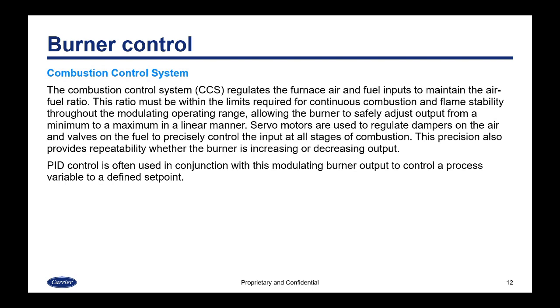The combustion control system regulates the furnace air and fuel inputs to maintain the air-fuel ratio. This ratio must be within the limits required for continuous combustion and flame stability throughout the modulating range, allowing the burner to safely adjust output from minimum to maximum in a linear manner. Servo motors are used to regulate dampers on the air as well as valves on the fuel. PID control is often used in conjunction with the modulating burner output to control a process variable to a defined set point.